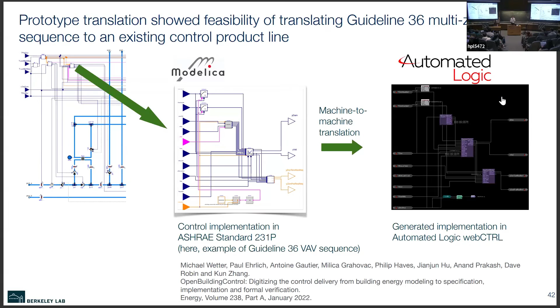The vision is that for our district energy application, we have these control blocks again for the district energy system, which also follow the ASHRAE Standard 231. So we can use the same machinery to translate this control logic to the respective building automation system that eventually will be selected for the installation.